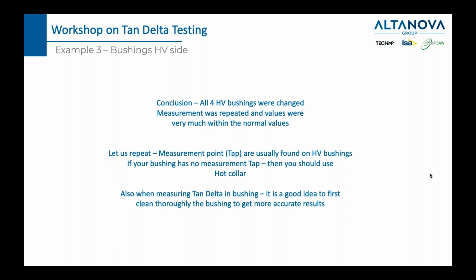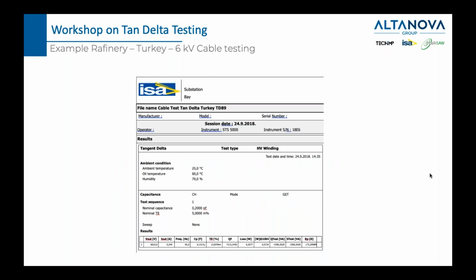You need to clean the bushing before doing that, but also in that case the interpretation of results will be slightly different, because 1% will probably not be reached, the values would be somewhat high. So this was the example which spoke about bushings.